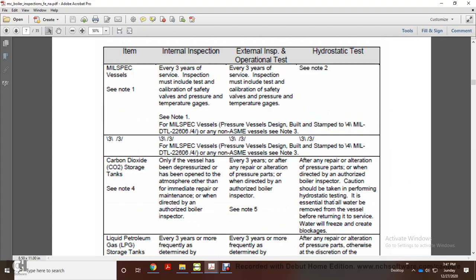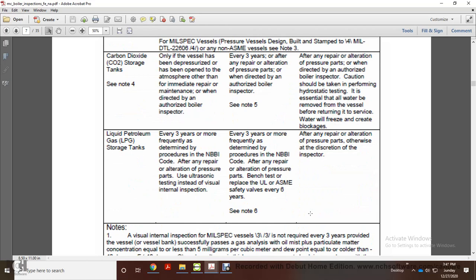Caution of the hydrostatic testing: it is essential that water be removed from the vessel before returning it to service. Water will freeze and create blockage. Liquid petroleum gas storage tanks every 3 years or more if determined with the procedure of the NBBI Code.